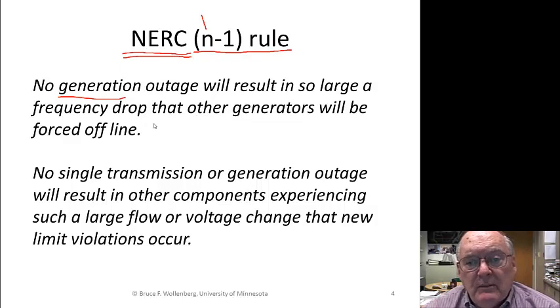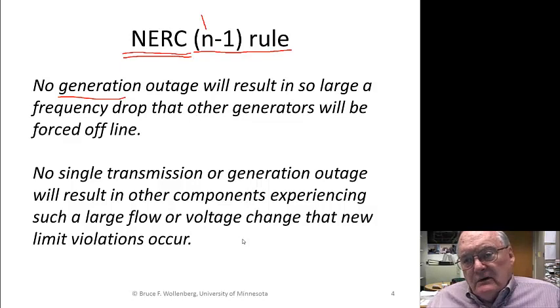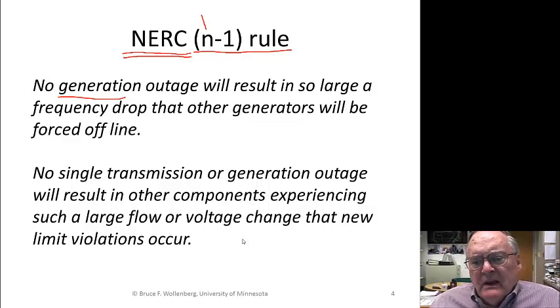So we have to worry about the generation outages. No single transmission or generation outage will result in another component's experiencing such a large flow or voltage change that new limit violations occur. Now what we're saying here is that if a generator goes out, or let's say a transmission line or transformer goes out, all the flows are going to change on the system, and many of the transmission lines will experience an increase in flow.